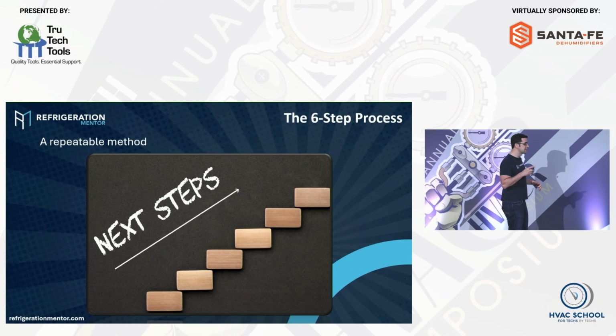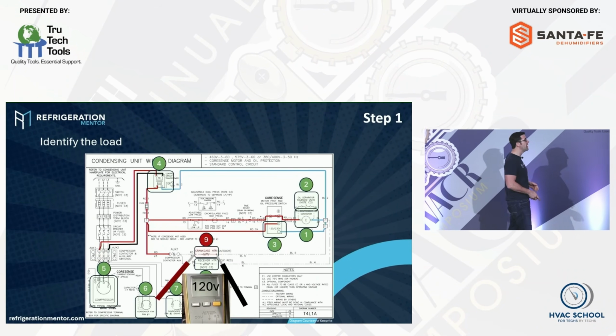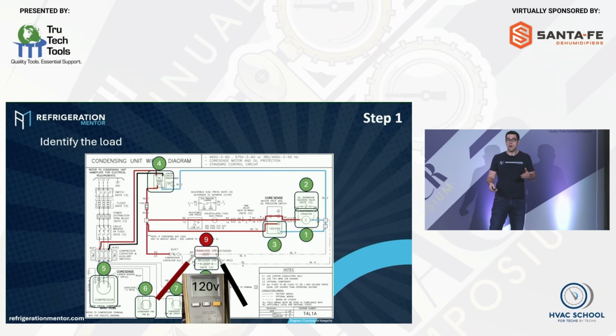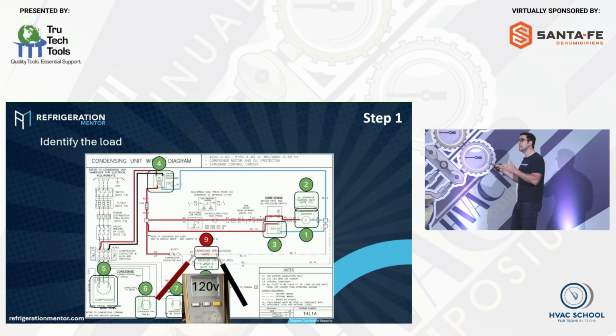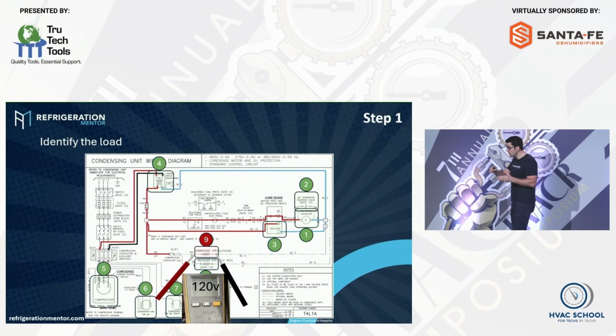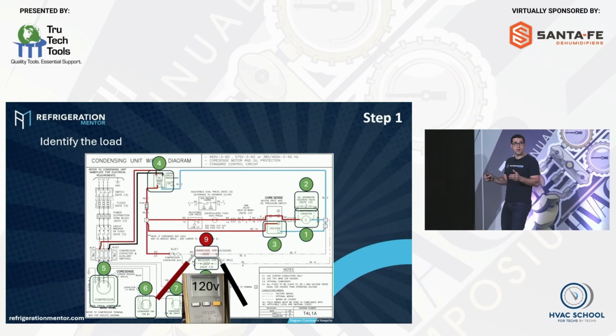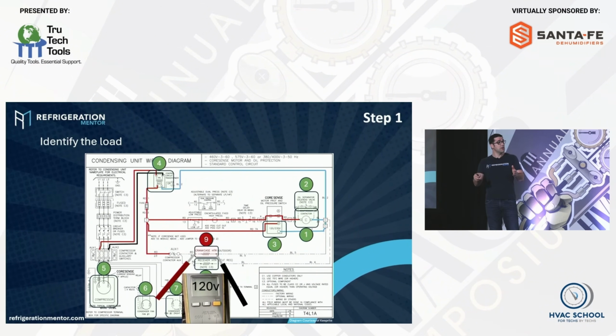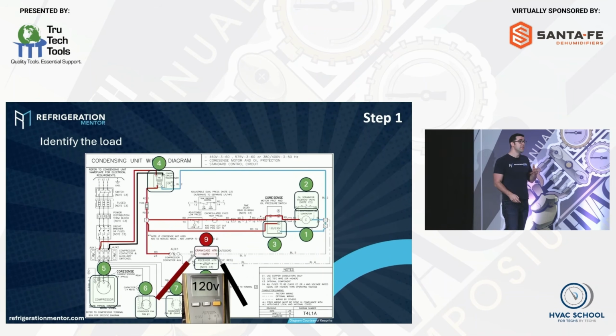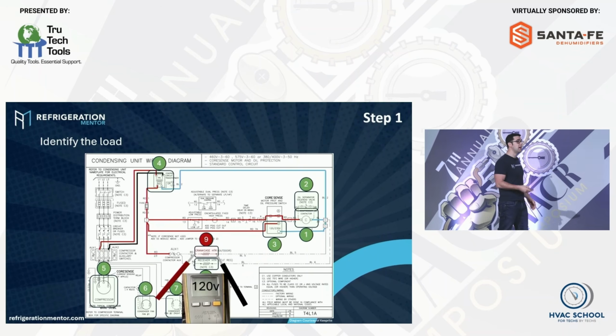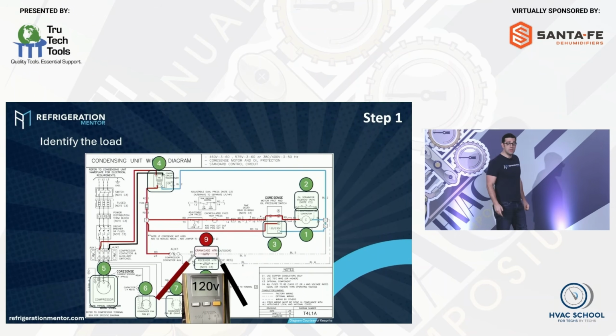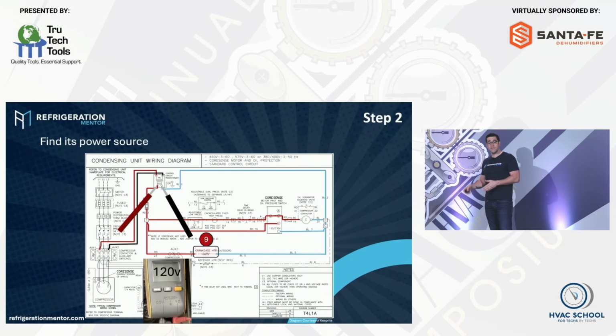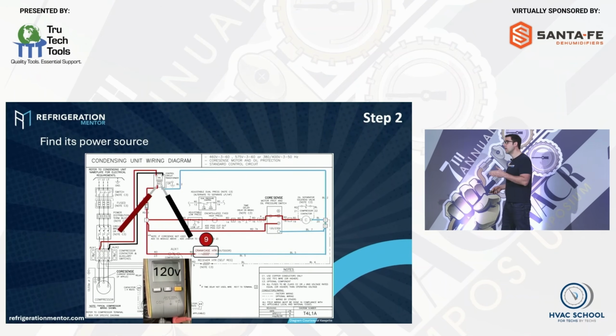And I'm going to talk about a 6-step process, a repeatable method, okay? Identify the load. What is the load in that? When you're looking at that wiring diagram, count right on it. This is what I do with all my students in my training program. I give them a wiring diagram. I'm like, circle all the loads on there. So if you know every one that's a load, on this example here, there's 9 loads in this condensing unit. Okay? Then you do the same thing for switches. And then you've got to find where the power is.